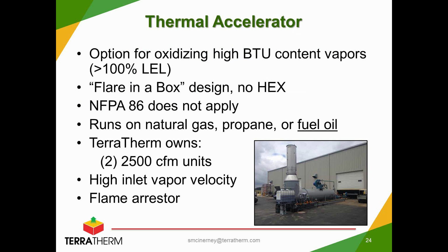This slide is really recognizing that there's another beast out there entirely when you're talking about thermal oxidation. TerraTherm currently owns 2 thermal accelerators. Essentially, it's a flare-in-the-box style design without a heat exchanger, and really well suited for high BTU content vapors. And these particular units are not governed by NFPA 86 in that they can operate at above 100% LEL. The units that we own can run on multiple fuel platforms, natural gas, they can run on propane, and they're currently deployed at a site where we're recovering jet fuel. And we're using that jet fuel that we recover at the site, conditioning that, and using that now as a supplemental fuel to fire these oxidizers.